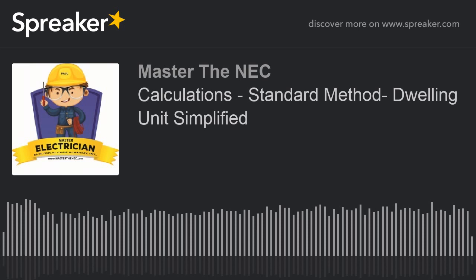So what you should have is 6150 for your general lighting and receptacle loads, because they do all associate a neutral. We have the fastened-in-place appliances. We only had 2 appliances that utilize a neutral. That was the dishwasher and the disposal. Okay, so that was 2328. Next, we had the dryer, which was 5,000 at 70%. That was 3,500.